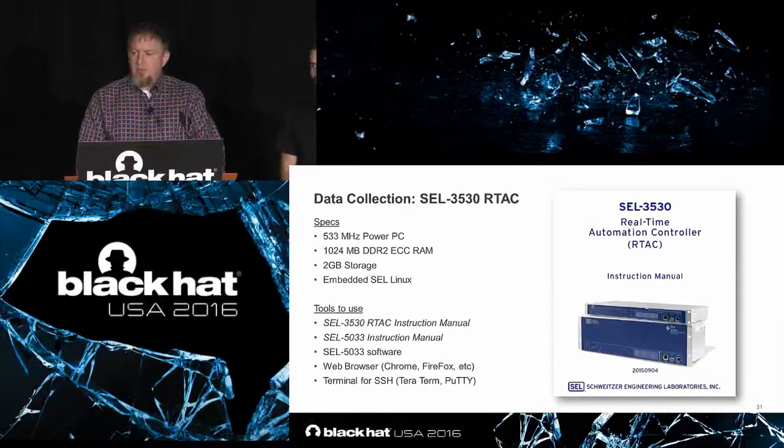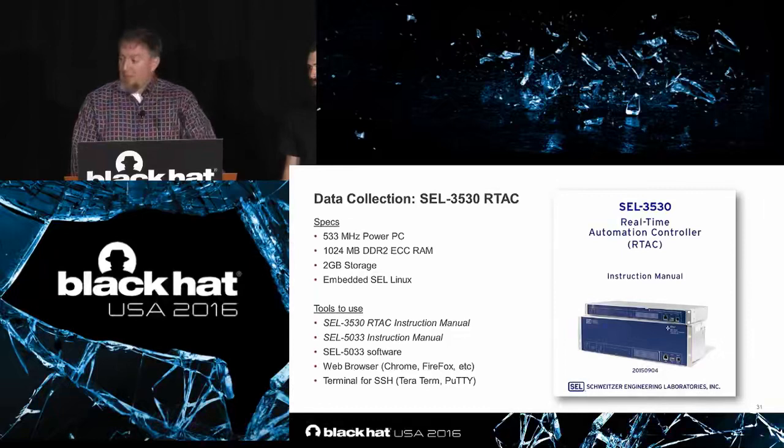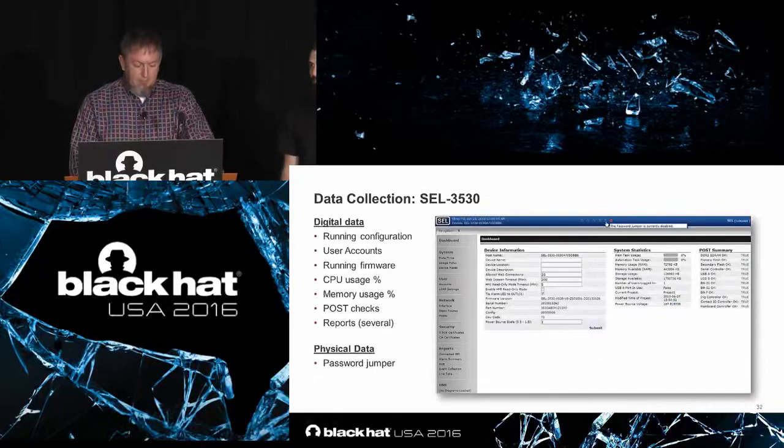RTAC is a real-time Linux, and it's also PowerPC related. It's got really great manuals, and you can get to it with a web browser in this case. Unfortunately, there's not a way to dump memory on this one, but we can still collect digital data, running configuration, user accounts, CPU usage, memory usage, post checks, and we can run reports.